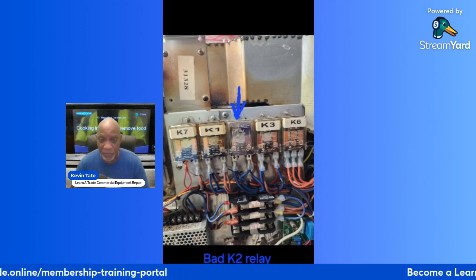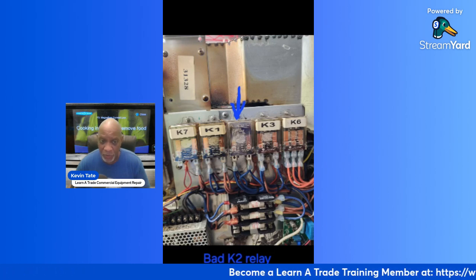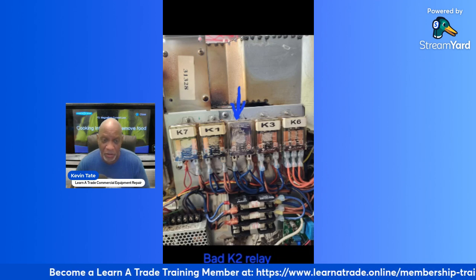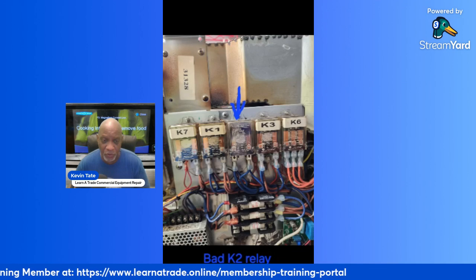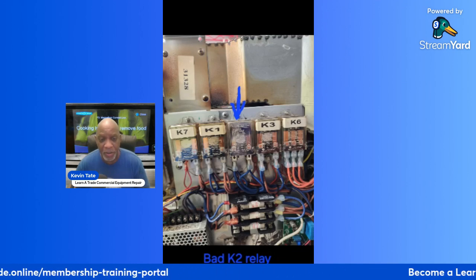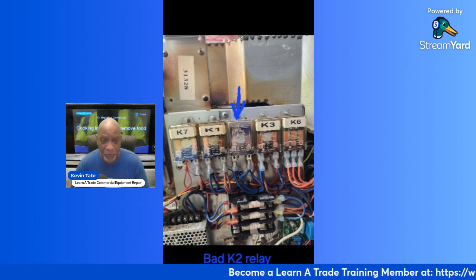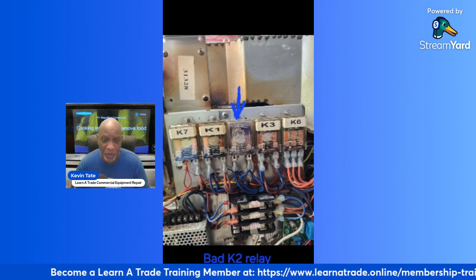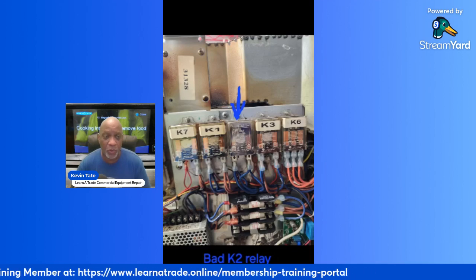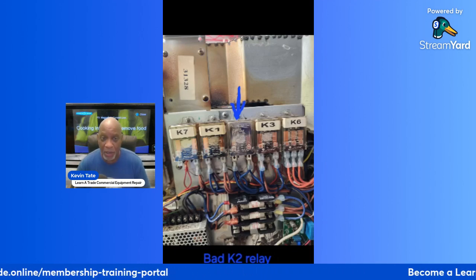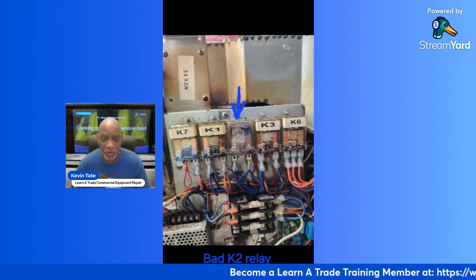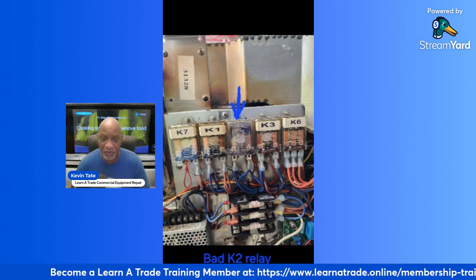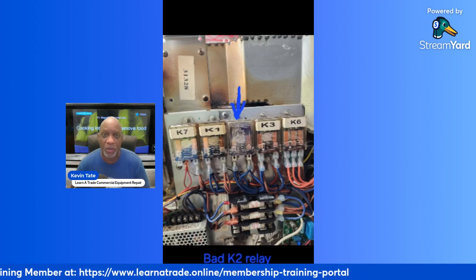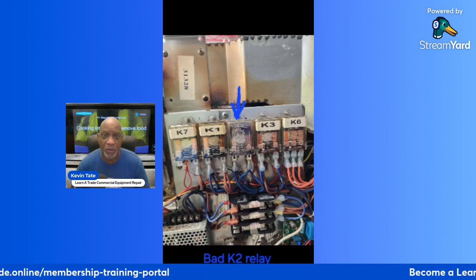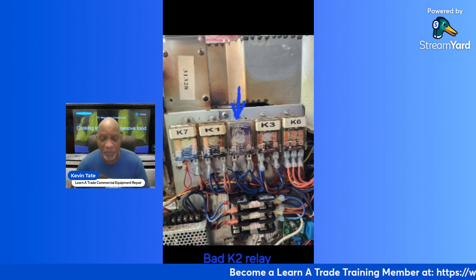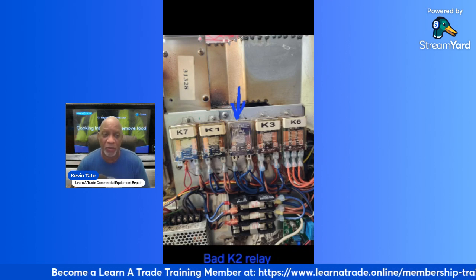And more than likely, if you have a bad relay, this fuse right down here, we'll be going over in a few. This is your 20 amp fuse. The next two fuses above that are 12 amp fuses. So you have a 12 amp fuse up top, a 12 amp fuse in the middle, and a 20 amp fuse or a 25 amp fuse on the bottom. On the Encore units, you usually want to use the 20 amp fuse. Those have always had 20 amp fuses in them. The newer model bullet units come with either a 20 amp fuse or a 25 amp fuse, depending on when they were manufactured.